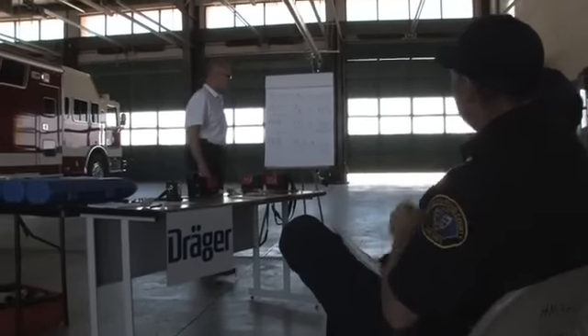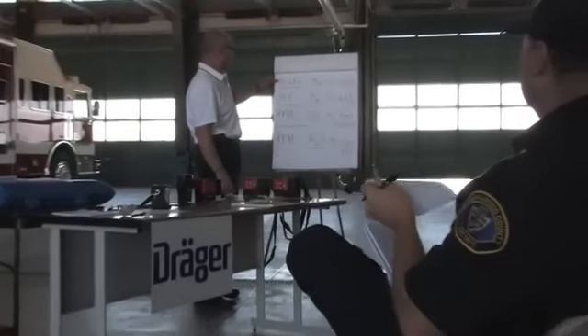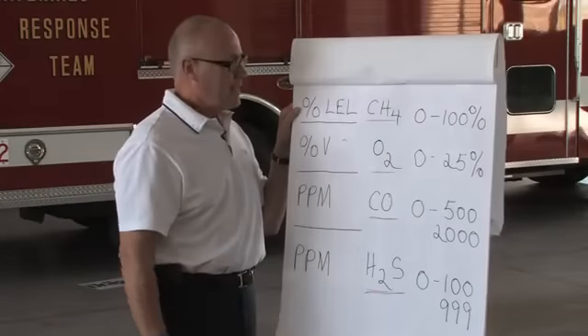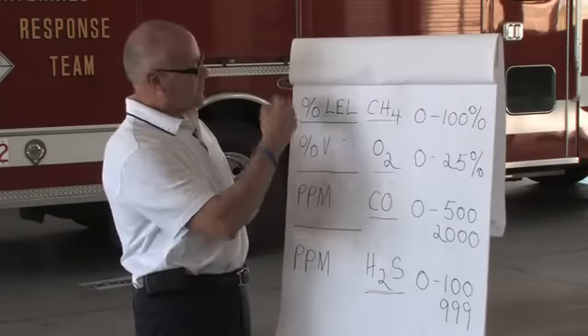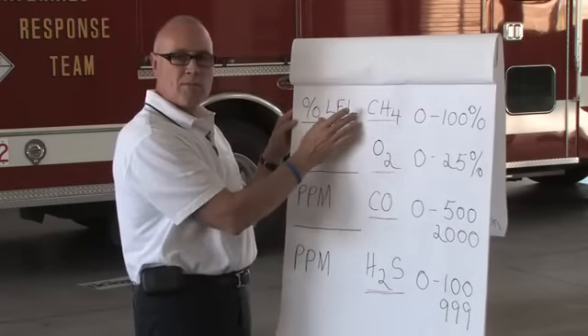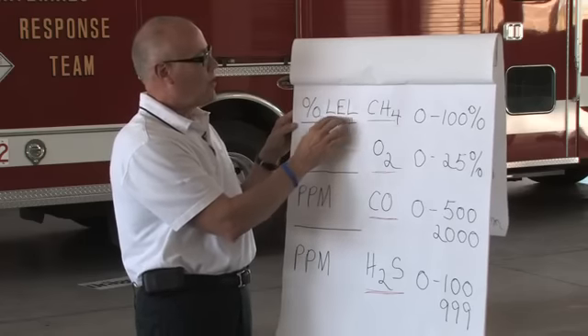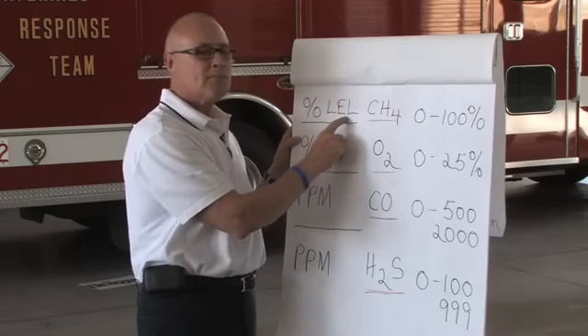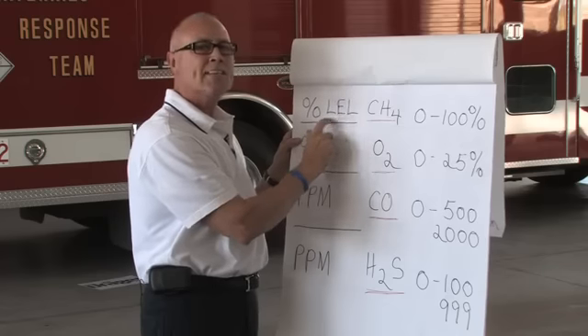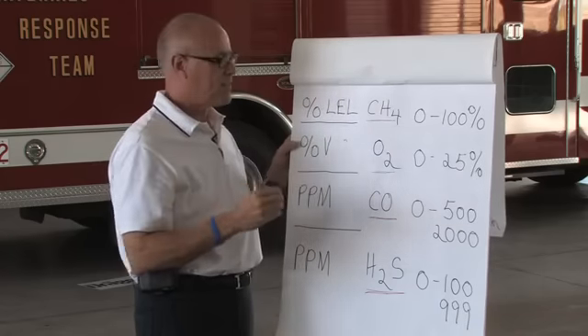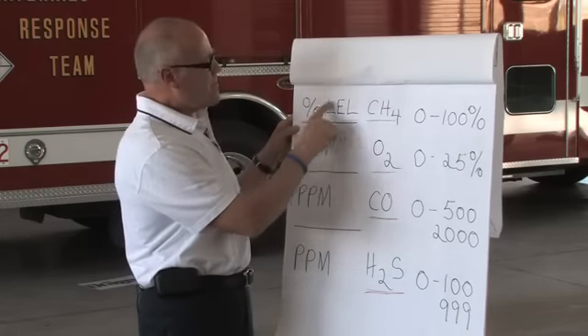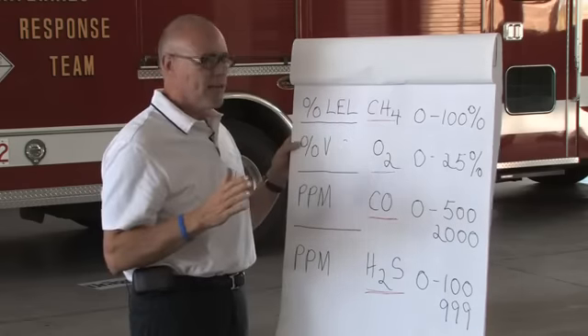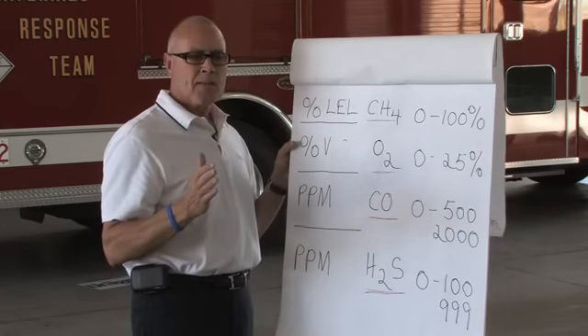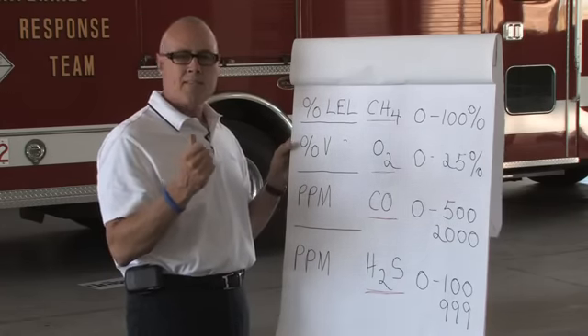Here is a chart that I wrote up on your scales for the 4 gases that are on your instruments. The LEL scale on the instrument is percentage of the lower explosive level or lower flammable level. You'll see LFL or LEL. They both, again, are synonymous. What this means is the lowest amount of gas or vapor to ignite.